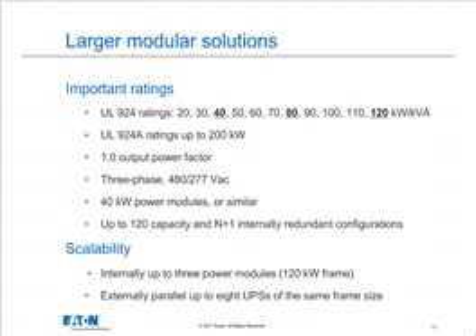So moving on, for larger solutions, we generally recommend a modular UPS that allows the customer to pay as they grow. If they add an extension to the building or a new wing to a hospital or something like that, I'd rather not rip out the emergency lighting system and all those batteries and have to start over again with something bigger. So, for example, on this page you see UPSs with ratings of 40, 80, 120, or 160 kVA. So I can start out with 40 and slide in an extra 40 into an existing enclosure and maybe add some batteries, but it allows me to build on the emergency lighting system that I have without starting over again with something larger. I do need to think about premises wiring that feeds that UPS to make sure I have enough capacity to handle that UPS no matter how big it may grow over the years.